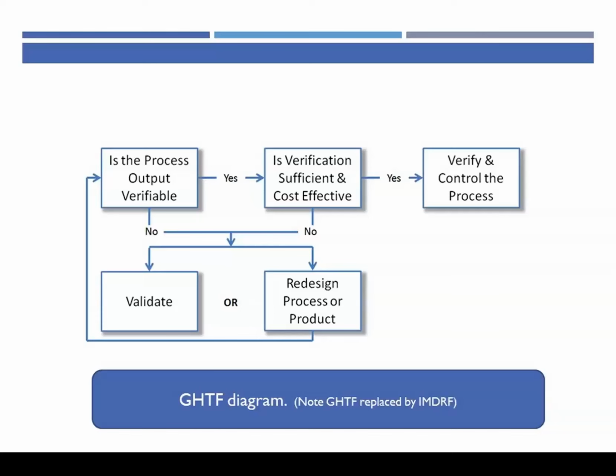Now today we don't use that term special process anymore because we've evolved our thinking and we don't want to have to rely on inspection to see if our product is good. We want to rely on validation. So the first question to ask yourself is the one in the upper left-hand corner. Is the process output verifiable? Can I physically measure or inspect every characteristic on that part to see if it's acceptable? And if the answer is no, then I have to validate, or I have to start over and redesign my product or process. But if I can't physically measure or inspect every characteristic, I have to validate.